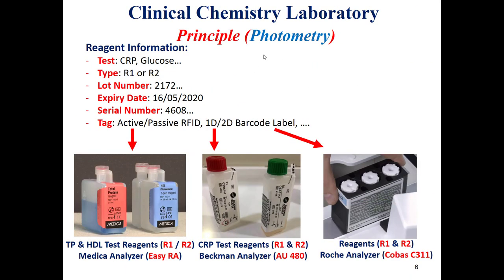Each reagent or analyte has a specific reagent with specific information. What information does the analyzer need to know about this reagent? Firstly, what is the type of test or analyte being tested — for example glucose, CRP, uric acid, and so on. We have two types of reagents, reagent 1 and reagent 2, and most analytes need two reagents. We should know whether it is R1 or R2 to preserve the sequence in adding the reagent with the analyte. We also need to know the lot number.